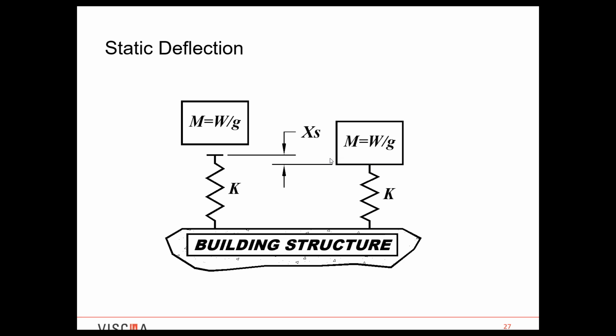And again, as John mentioned earlier, it is confusing once you get into spring isolators, especially because spring isolators in our industry can have a preload at some point. Just because you're talking about a 4-inch deflection spring or a 2-inch deflection spring does not necessarily mean that spring is going to deflect that amount after it's already loaded. So we get into terms like differential deflection, and that's the deflection that you're going to see after the isolator is loaded.